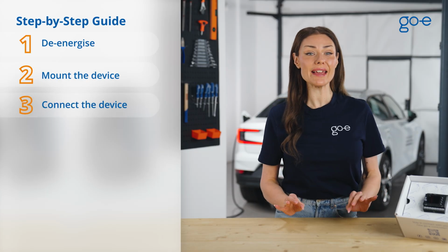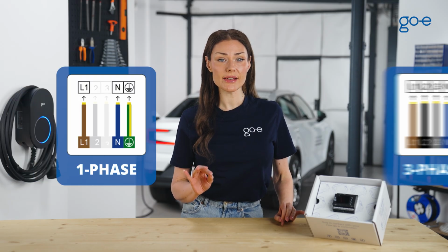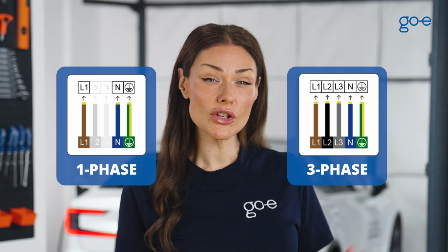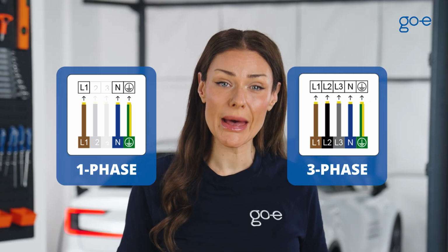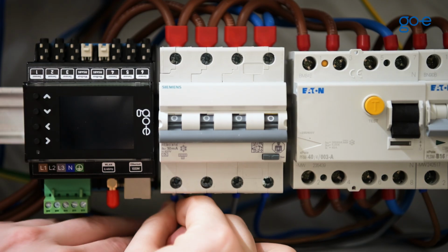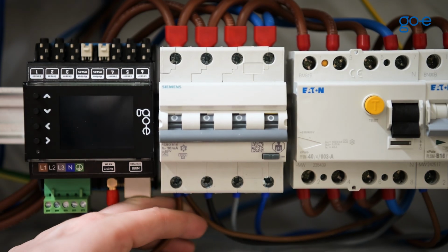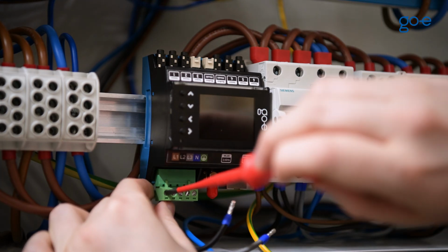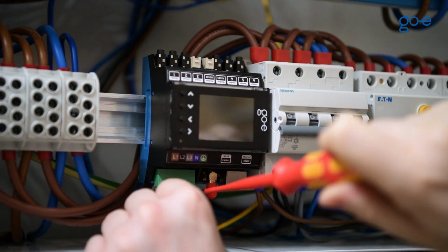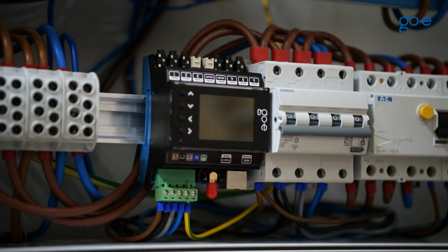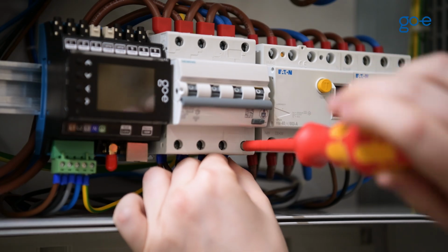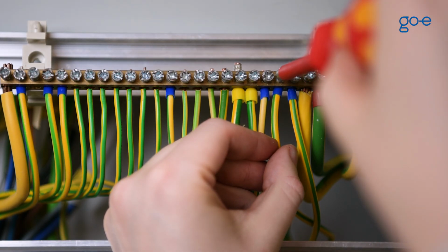Step 3. Now connect the GoE controller with either a single-phase or 3-phase connection. The controller itself consumes hardly any power, so it can also share a circuit breaker with other devices, for example, a kettle or an electric cooker. If that's not possible, you'll need to install a new circuit breaker. Always make sure to follow local installation standards. Insert the conductors into the connection terminal of the GoE controller and secure them with a screwdriver. Also, connect the neutral conductor and the protective earth conductor.